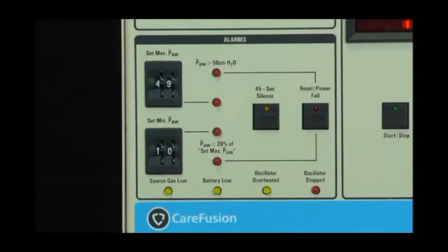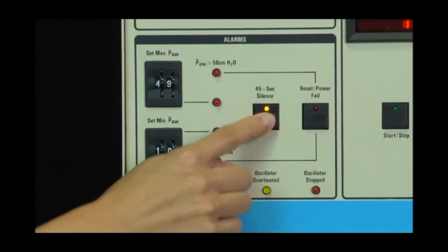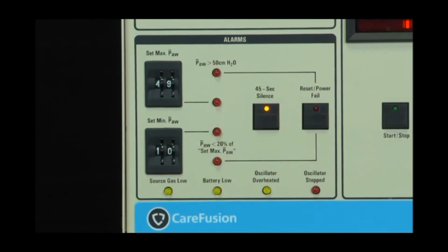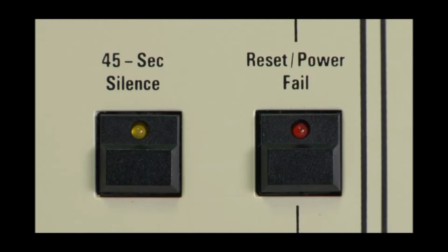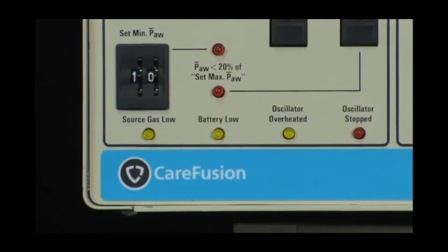The Alarm Silence push button silences all audible alarms for 45 seconds. Once activated, this button illuminates a yellow LED. The alarm silence will remain active for the full 45 seconds. The power fail alarm provides an audible and visual signal, indicating loss of electrical power to the ventilator. This alarm is also triggered when the ventilator is powered off. To silence it, press the Reset Power Fail button. These three yellow LEDs are caution indicators, with no accompanying audible alarm.